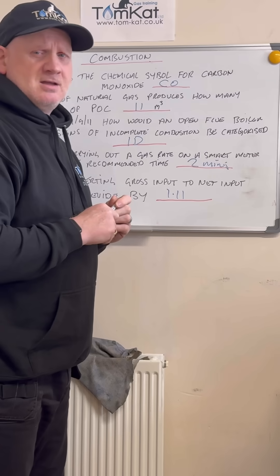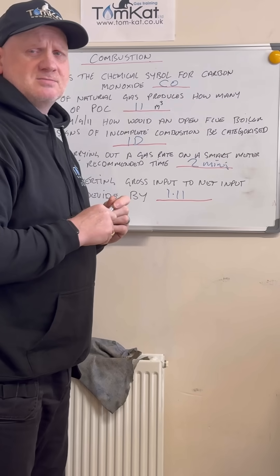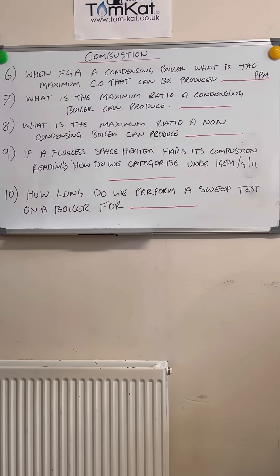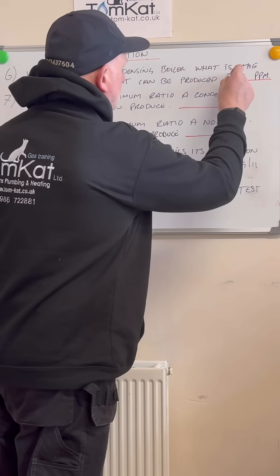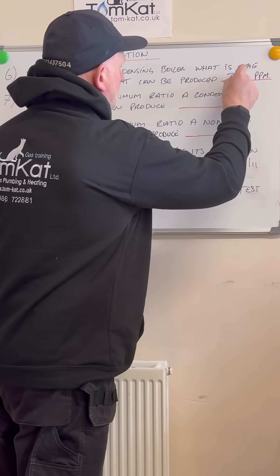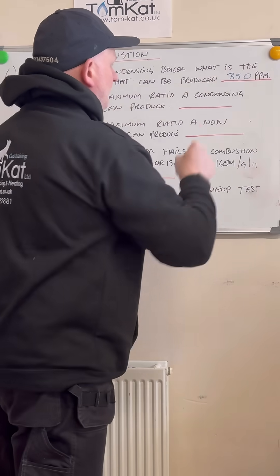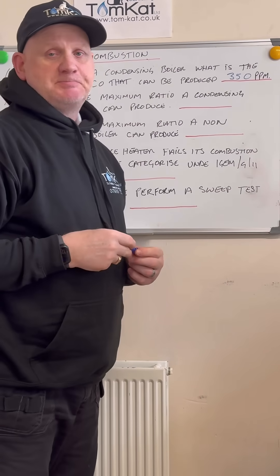Let's have a quick question six. When flue gas analyzing a condensing boiler, what is the maximum CO that can be produced? Hopefully you put 350 parts per million.